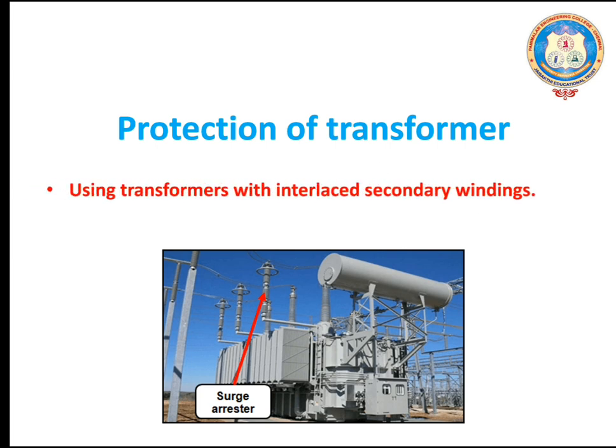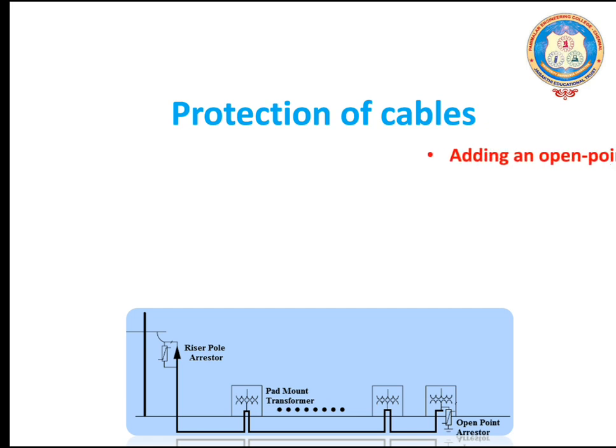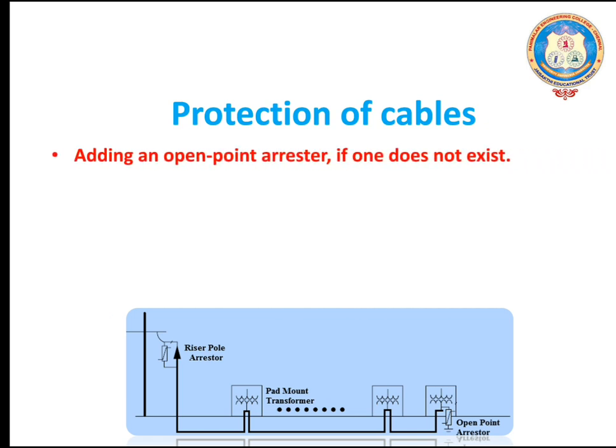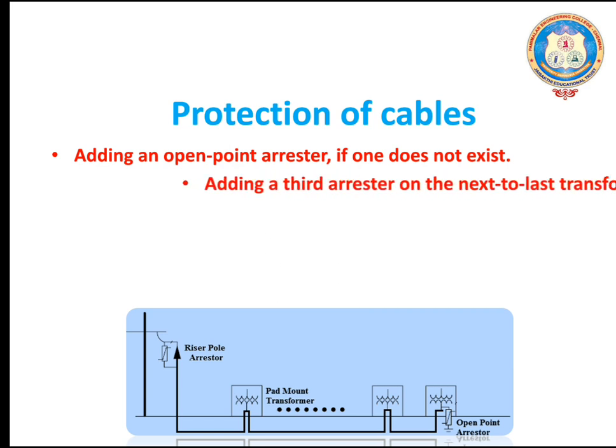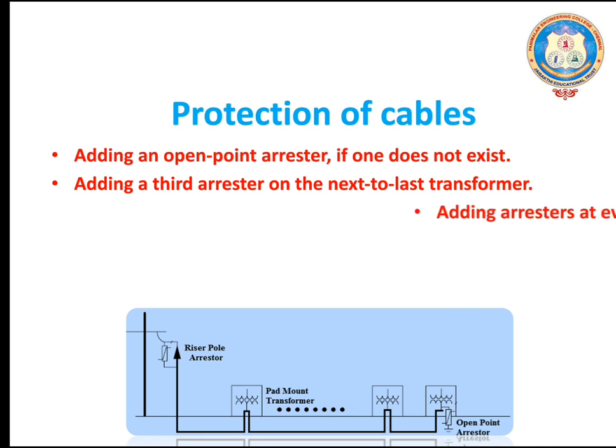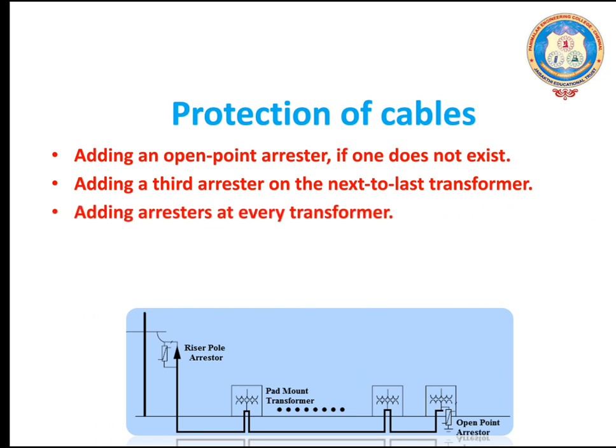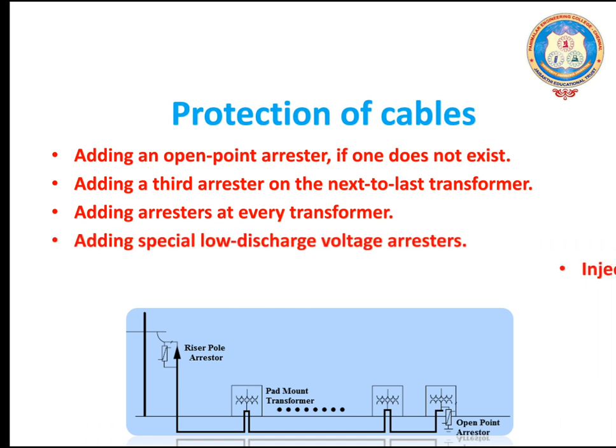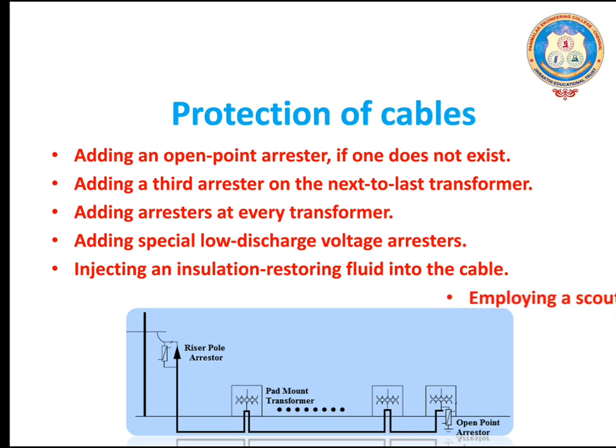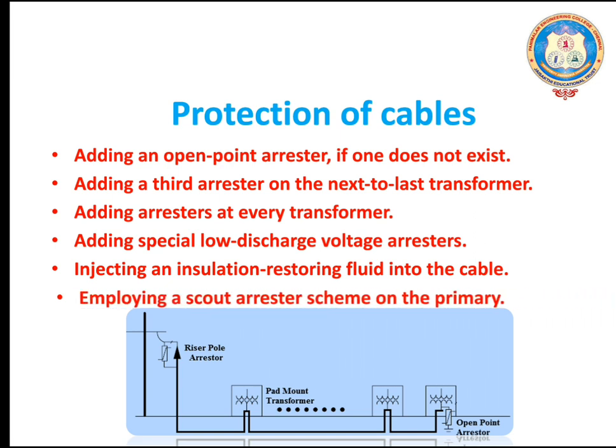How are transformers protected? Transformers are protected by using interlaced secondary windings and having surge arrestors at the X-terminal. How are cables protected? By adding an open-point arrestor, by adding a third arrestor on the next-to-last transformer, by adding an arrestor at every transformer, by adding special low-discharge voltage arresters, by injecting an insulation-restoring fluid into the cable, and by employing a scout arrestor scheme on the primary.